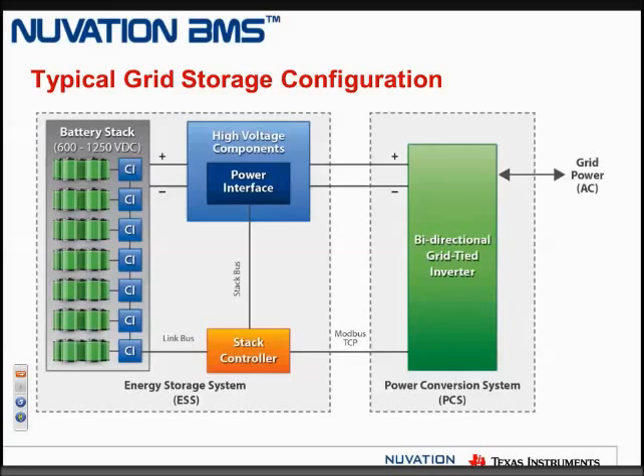So the stack controller brings all this together because it talks to all of these components. It's hooked up to the cell interfaces for measurement and control of the cells, and it's powered from the power interface, allowing overall measurement of the battery at the stack level. It also communicates to the inverters and other equipment within that local grid site to run the whole system in a way that keeps the batteries happy. That's often done in a lot of applications, and we're seeing that as Modbus TCP to the inverter.